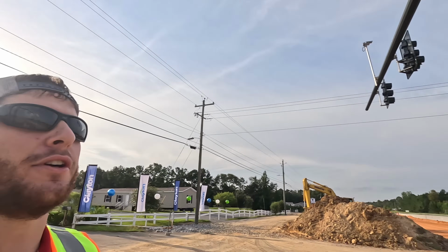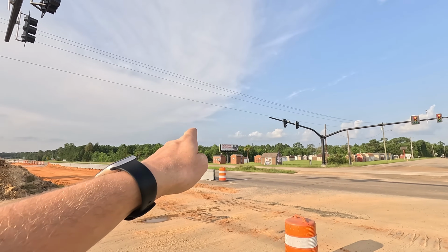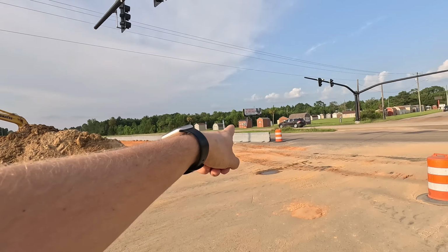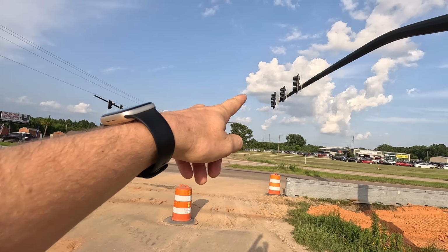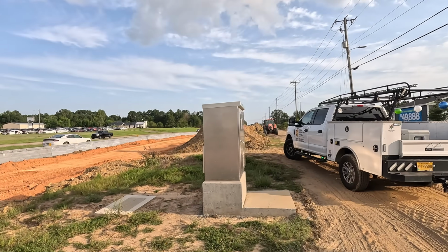Today we are responding to a call at this intersection because people are not getting the green light at this left turn lane. I know for certain that they are getting vehicle calls and should be getting the green light, but the controller's not allowing phase one, which is that left turn lane for this flashing yellow arrow up here, to get the green light. So let's get inside this traffic signal controller cabinet and take a look.